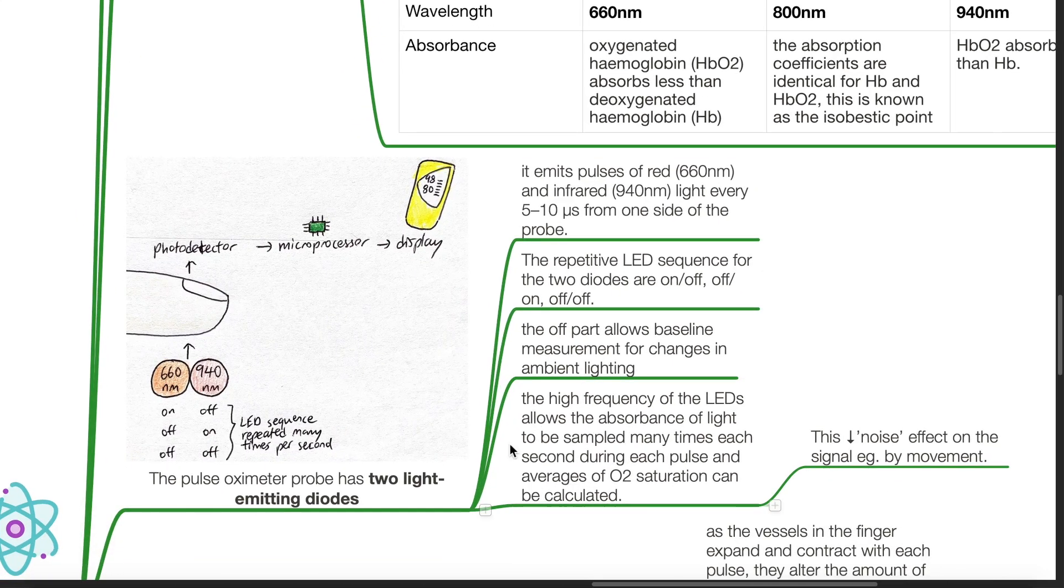The pulse oximeter probe has two light emitting diodes, and it emits pulses of red at 660 nm and infrared at 940 nm light every 5 to 10 microseconds from one side of the probe. The repetitive LED sequence for the two diodes are on-off, off-on, and off-off. The off-off part allows baseline measurement for changes in ambient lighting.